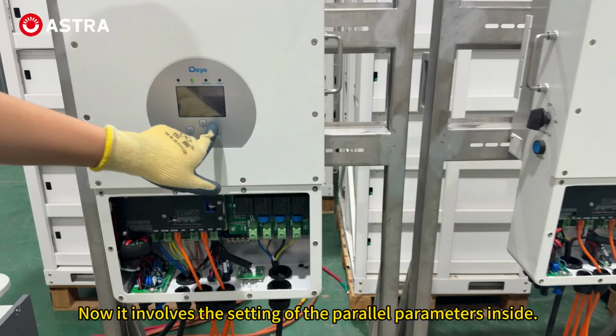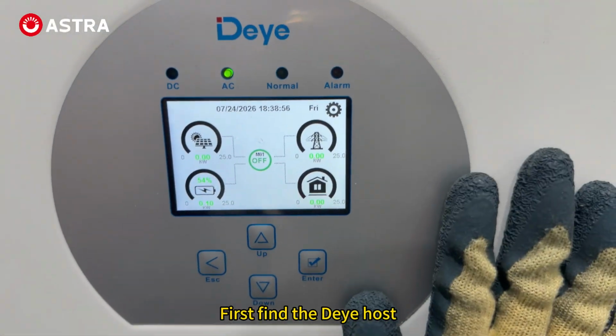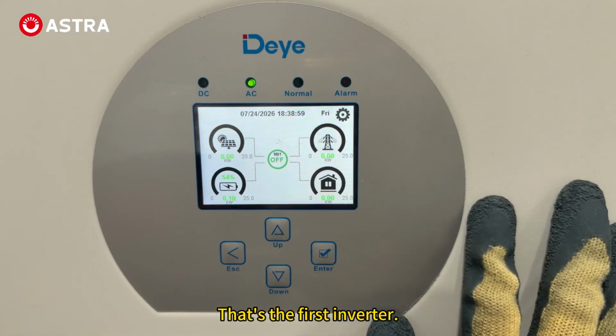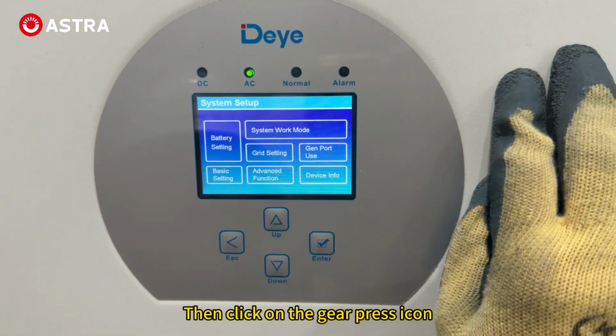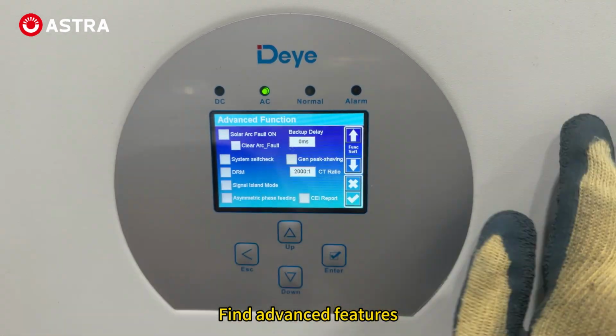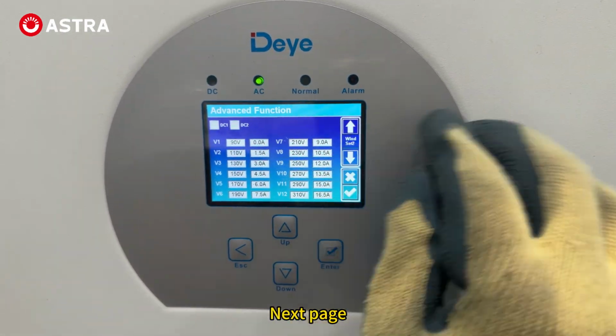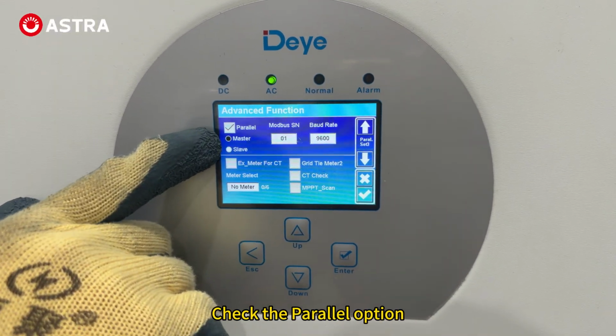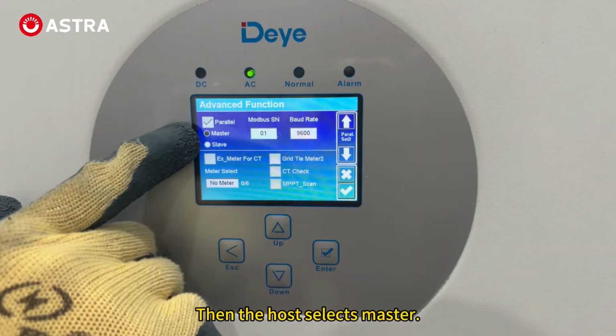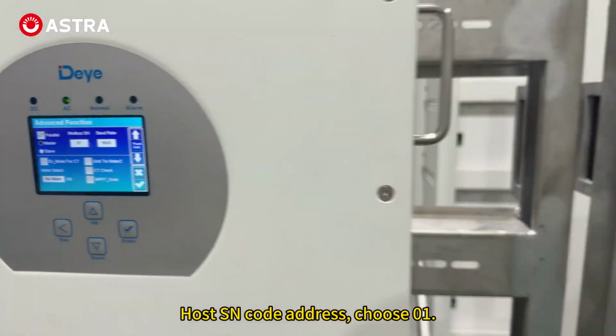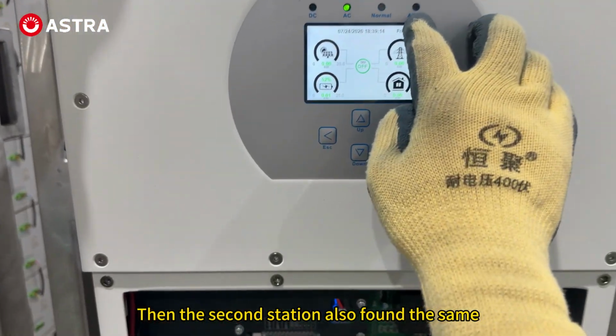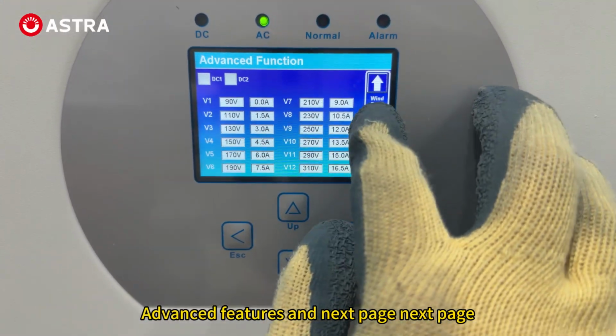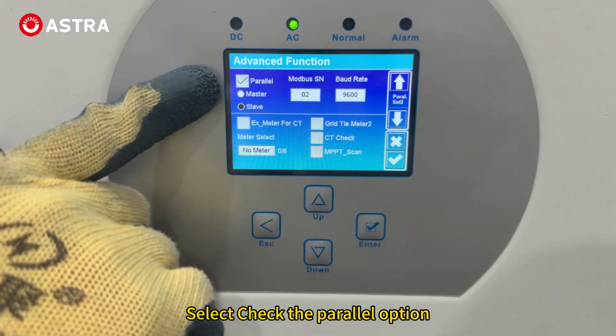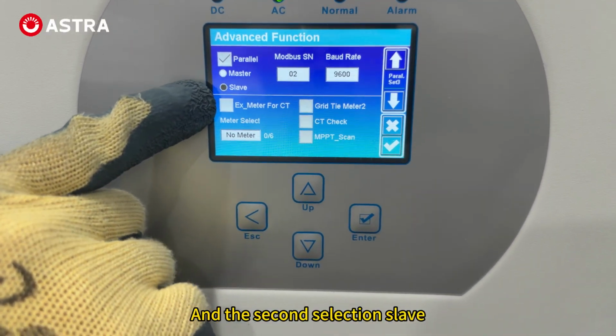Now it involves the setting of the parallel parameters. First, find the host, that's the first inverter. Then click on the gear icon. Find advanced features, then the next page. Then check the parallel option. Then the host selects master. That's the host setup. For the host SN code address, choose 01. Then on the second one, also find advanced features and the next page. Check the parallel option. And the second one selects slave. Then select 02 for the address.